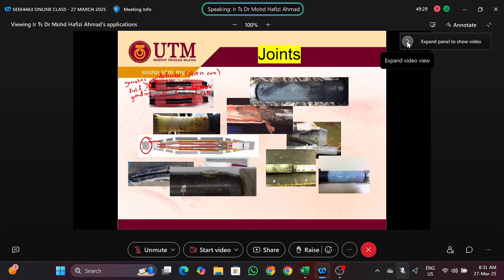So what happens if they are not installed the correct way? You might see this kind of surface tracking, something like electrical trees that may propagate, crawling on the surface, and finally short circuit between these two conductors. And then of course a flashover may happen, so the cable may break down. So this is what we don't want to happen.